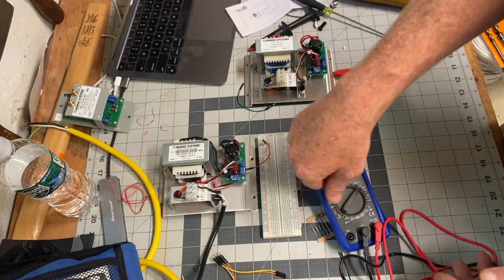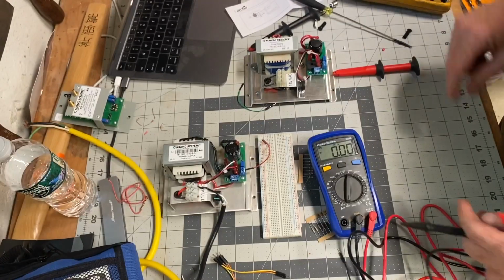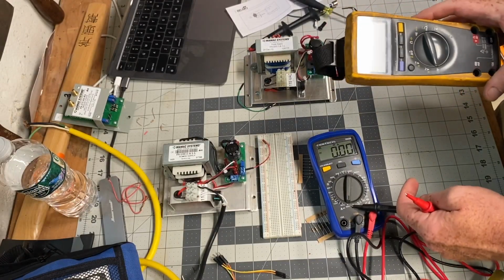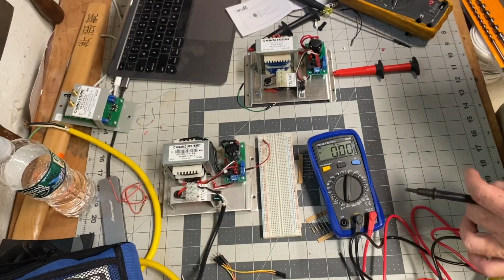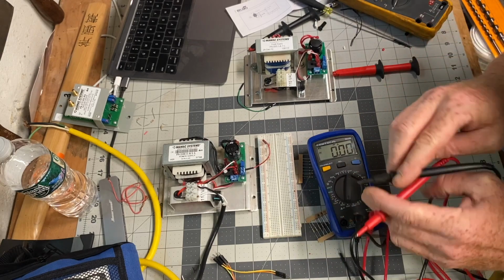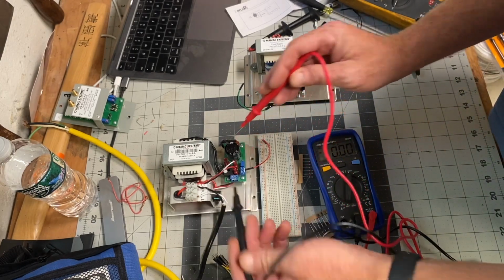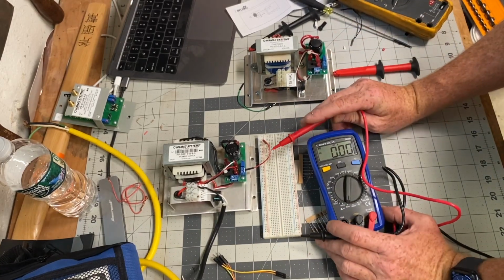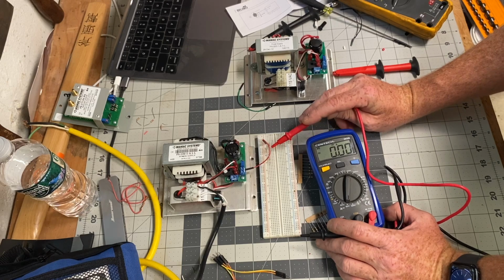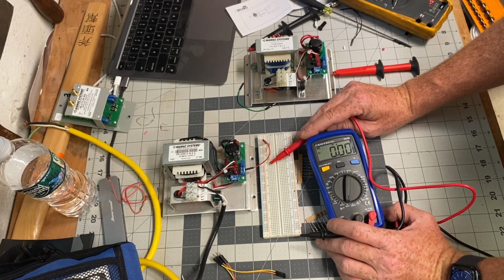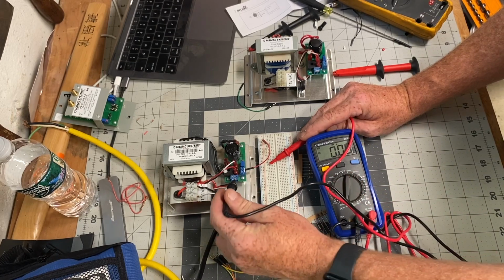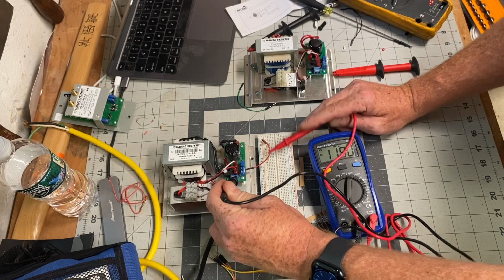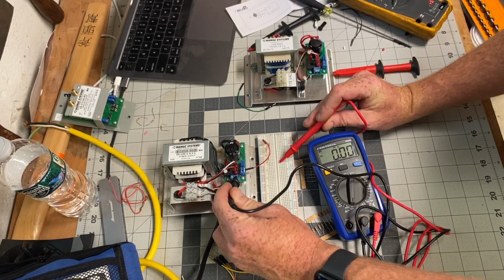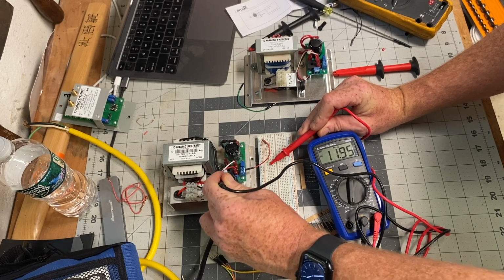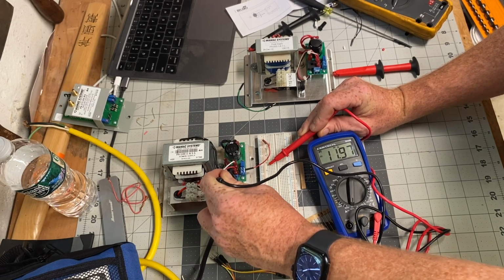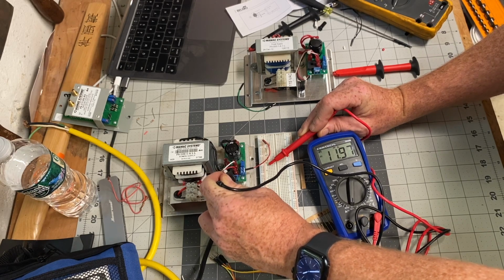So if I switch this over to milliamps, as far as the meter, I don't have to switch the probe, so I can leave that probe there. Just switch it over to 60 milliamps. How I blew up the meter last time was I went straight across that. Oops. But here we're sending 24 volts into a 2000 ohm resistor. So with 2000 ohms at 24 volts DC, and I read the milliamps back, I should have 12 milliamps. I got 11.98, 11.97, so we're right there.